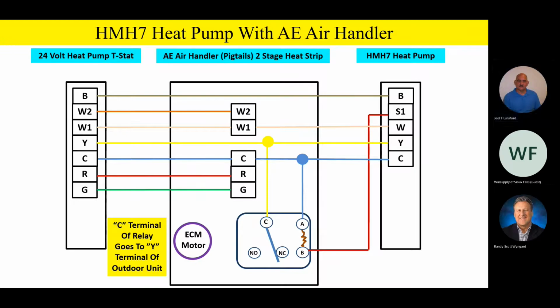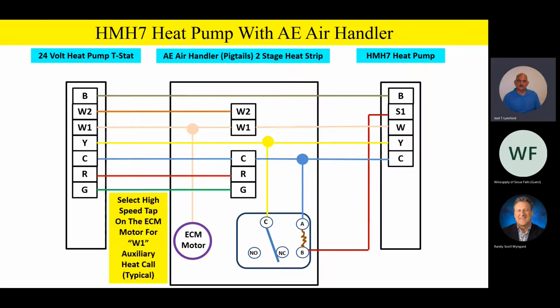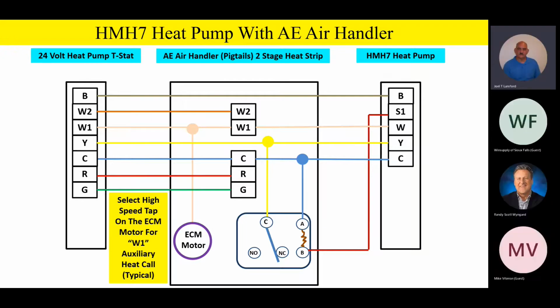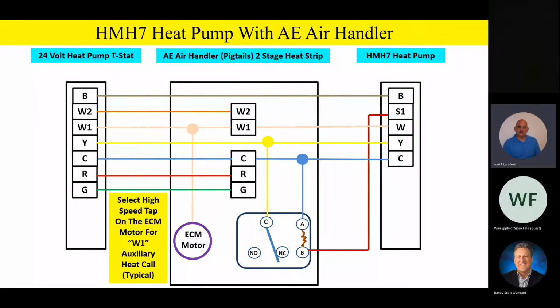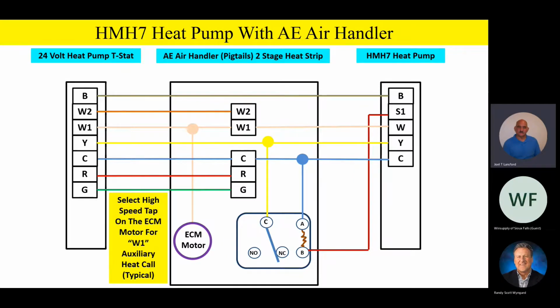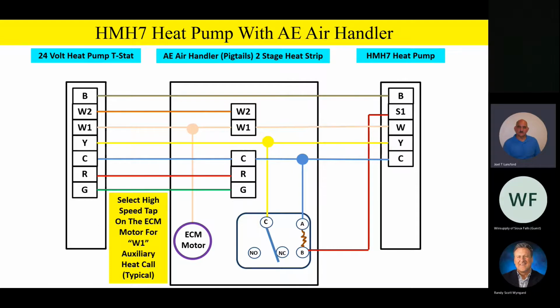Now, a very, very typical way to hook this up as well on the ECM motor is to go ahead and take speed tap number 5, which is typically your high speed tap, take your high speed tap on the motor and just manufacture a wire or go up and hook up the high speed on the ECM motor to your W1 call.